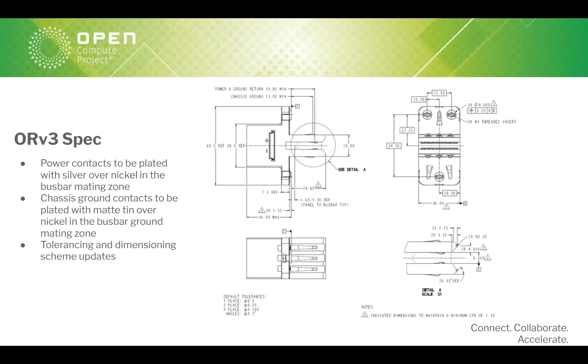Some additional updates to the spec: the plating has been defined. The power contacts are to be plated with silver over nickel in the bus bar mating zone, and the chassis ground contacts are to be plated with matte tin over nickel in the bus bar ground mating zone. The last bullet references the tolerancing and dimension updates made to the views shown here, which are in the uploaded spec.